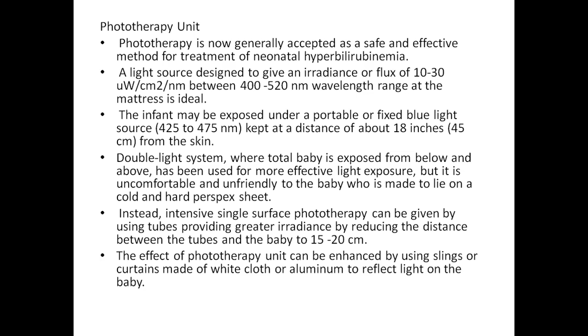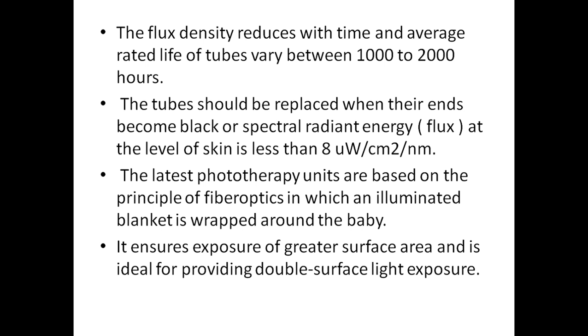Instead, intensive single surface phototherapy can be given by using tubes providing greater irradiance by reducing the distance between the tubes and the baby to 15 to 20 centimeters. The effect of the phototherapy unit can be enhanced by using slings or curtains made of white cloth or aluminum to reflect light on the baby. The average rated life of tubes varies from 1000 to 2000 hours. The tubes should be replaced when the ends become black or the spectral radiant energy at the level of skin is less than 8. The latest phototherapy units are based on the principle of fiber optics, in which a illuminated blanket is wrapped around the baby. It ensures exposure of a greater surface area and is ideal for providing double surface light exposure.